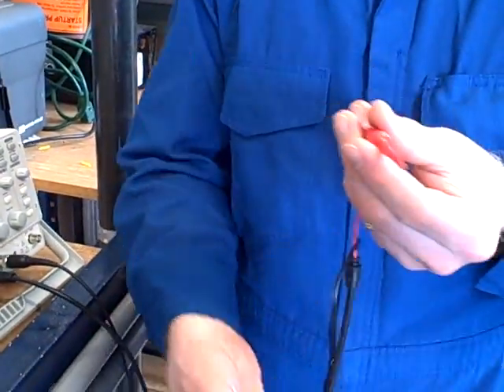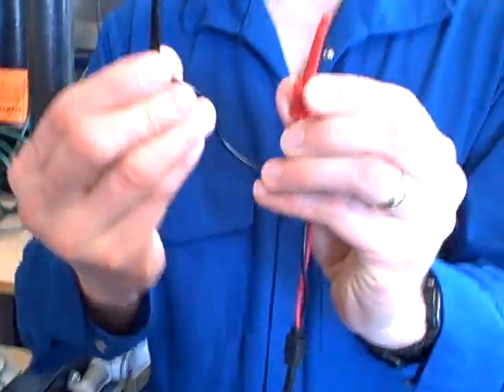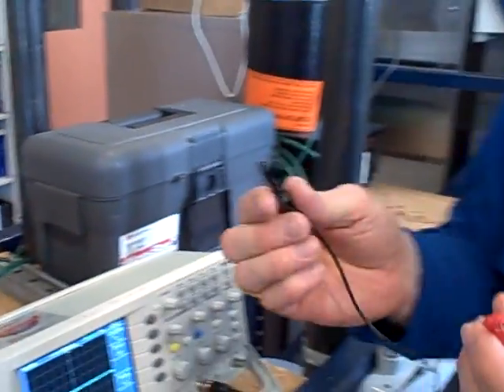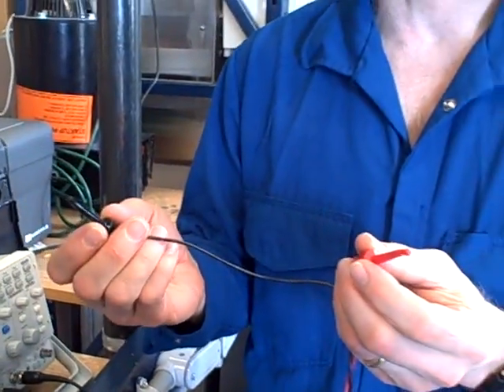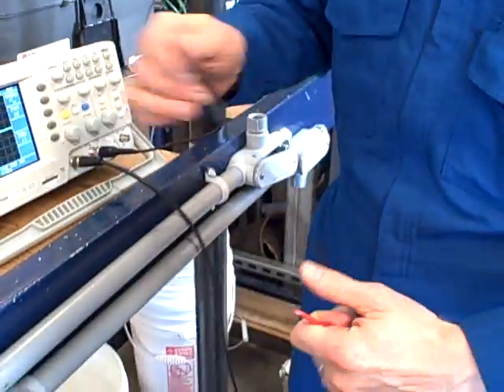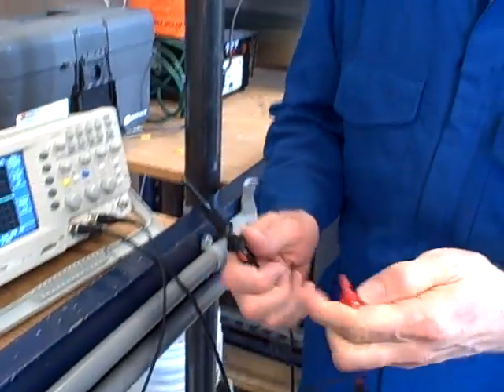If I simply took one channel here with my probe and ground and I went across the field bus, I would be grounding one of those field bus conductors. I do not want to do that. So I want to do a differential measurement as opposed to a ground referenced measurement.